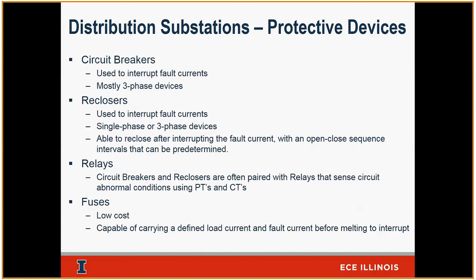So it's not a very expensive device, not a big recloser, right? What a fuse does, it's got a melting characteristic. So it can handle current and temperature. And as that temperature goes up, when you have a fault, that causes excessive heating. And based on that fault, that has a melting characteristic and it will melt and it will pop open. That's what a fuse does. So the engineer will decide what is that limiting factor per that tap.